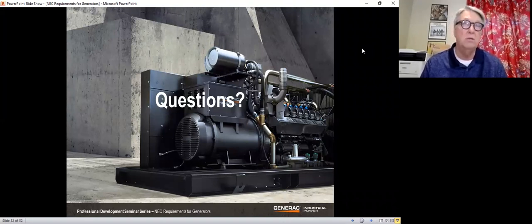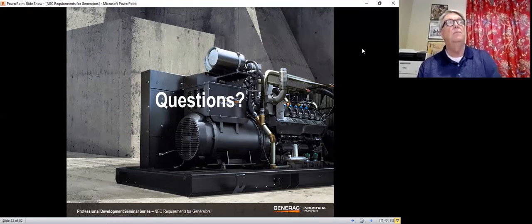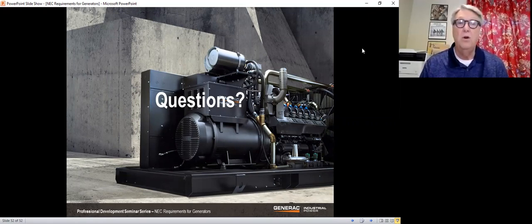And in the case of a solar system, there are just so many different ways of doing a solar system that the only thing I can really tell you is you're going to have to look at the particular type of solar system that you have and look at the system connection diagram before you'll know how you can connect that together. There's just not a simple rule that I can tell you. But typically, unless you have isolation in there, you're going to do your neutral to ground bond at the utility, and no one else would have a neutral to ground bond. All the neutrals would go to the neutral bus bar if it was going through the transfer switch. If it's not going through the transfer switch, then of course that's immaterial.